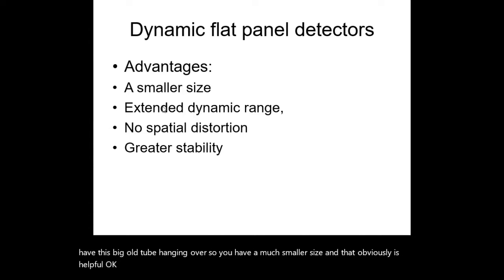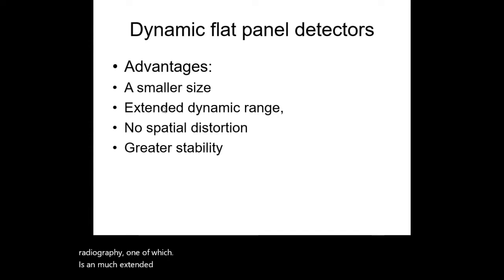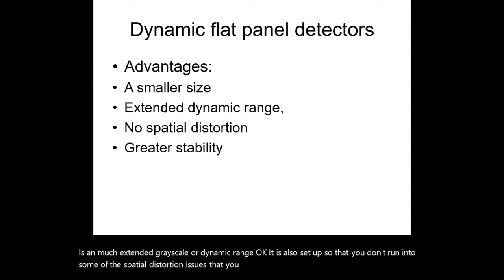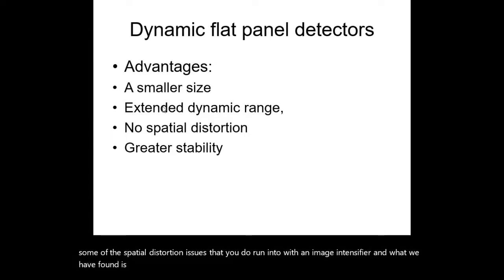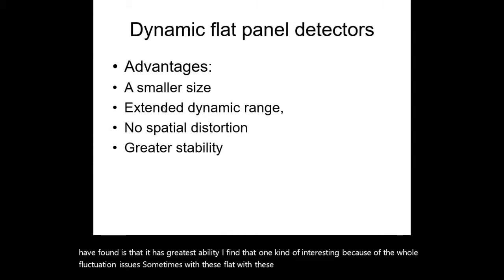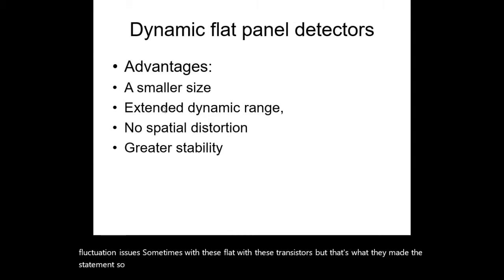Like any flat panel detector, you have the same advantages as you do with digital radiography, one of which is a much extended grayscale or dynamic range. It is also set up so that you don't run into some of the spatial distortion issues that you do run into with an image intensifier. And what we have found is that it has greater stability. I find that one kind of interesting because of the whole fluctuation issues sometimes with these transistors. But that's what they made the statement, so I'm just reporting.